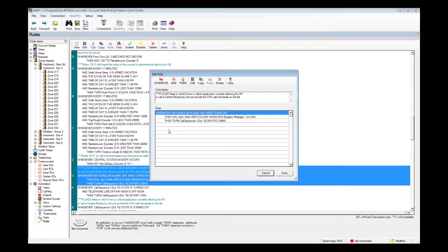I would go ahead and call everyone within the one rule, just so that the M1's doing what it's supposed to. It's calling, it's waiting, you know, everyone's going to get a phone call. Some people want to call, and if the call is acknowledged, then stop the calls. You can do that, and what we've done is use a call sequence scenario. And when the alarm turns on, we dial John, we speak the message. We're turning on a phantom output for 3 minutes. Okay.